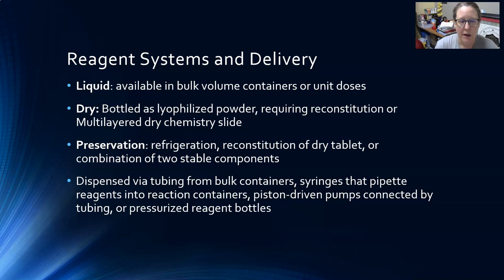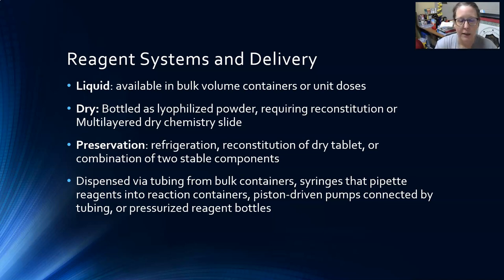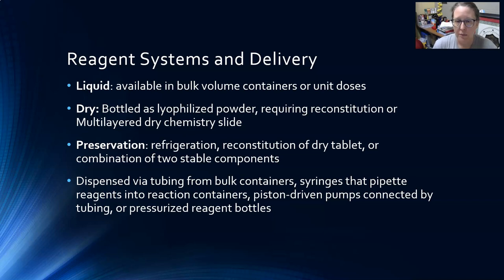Next is the reagent systems and delivery phase. Reagents can be liquid or dry. Liquid reagents can be in bulk volume containers or unit doses — small containers of reagents for a set number of tests. When dry, they can be bottled as a lyophilized powder requiring reconstitution, which can be done by the analyzer by adding water if it's a wet analyzer with access to clinical lab reagent water, or it might have to be reconstituted by the tech.